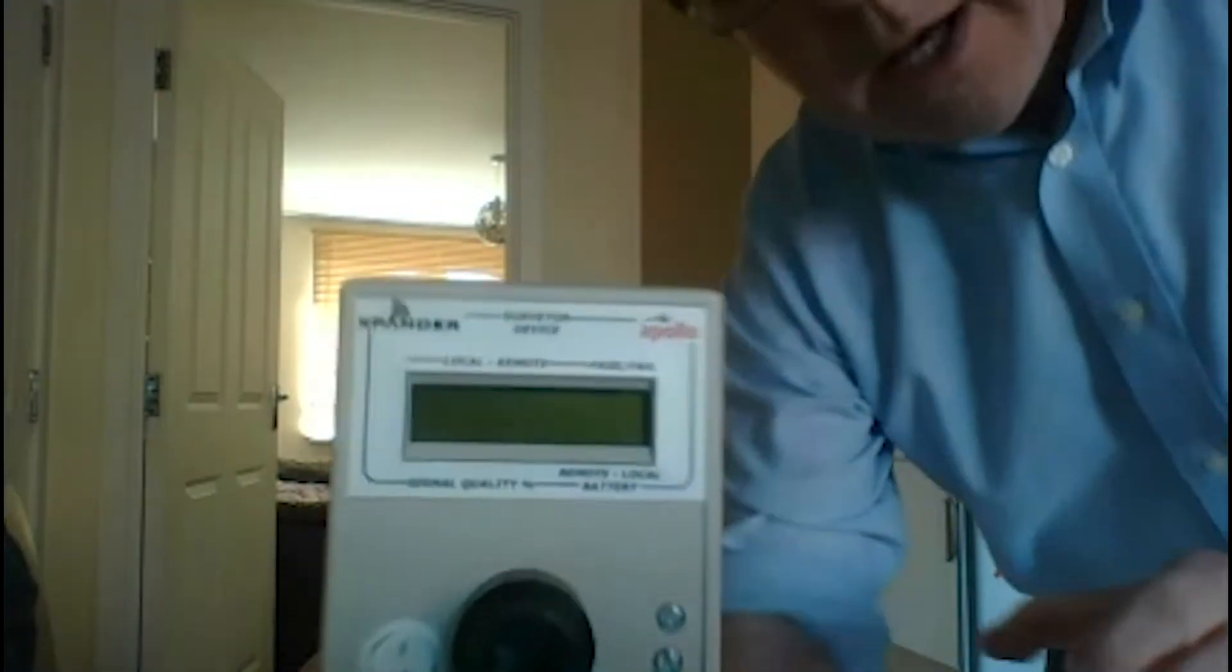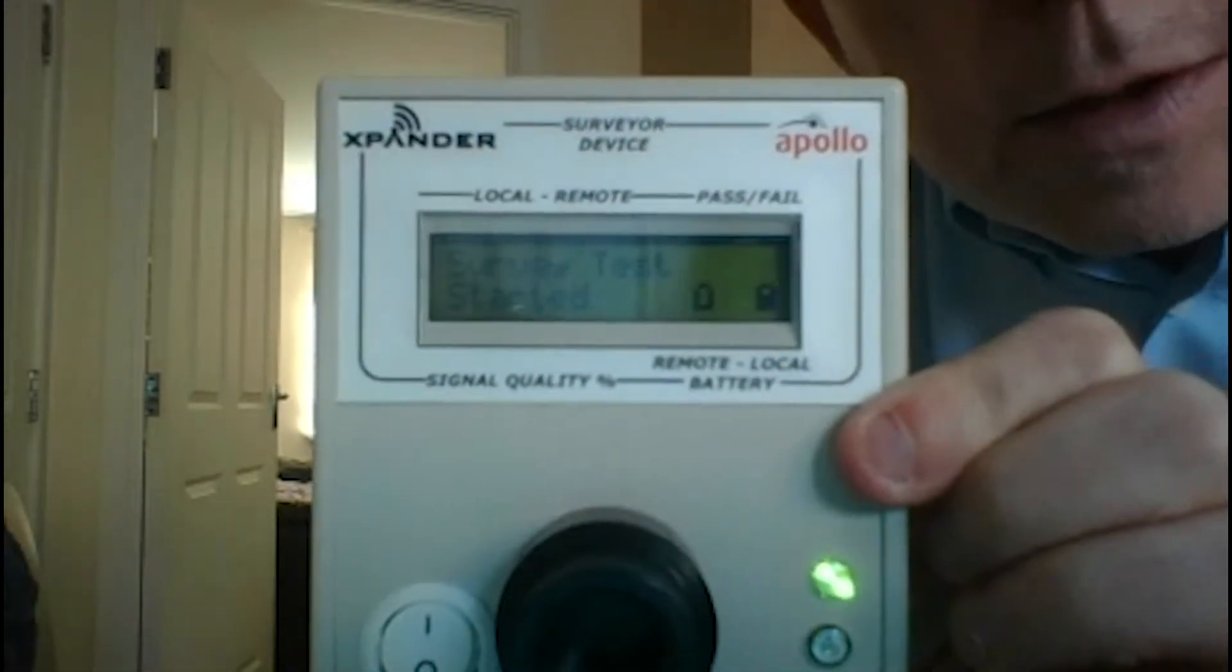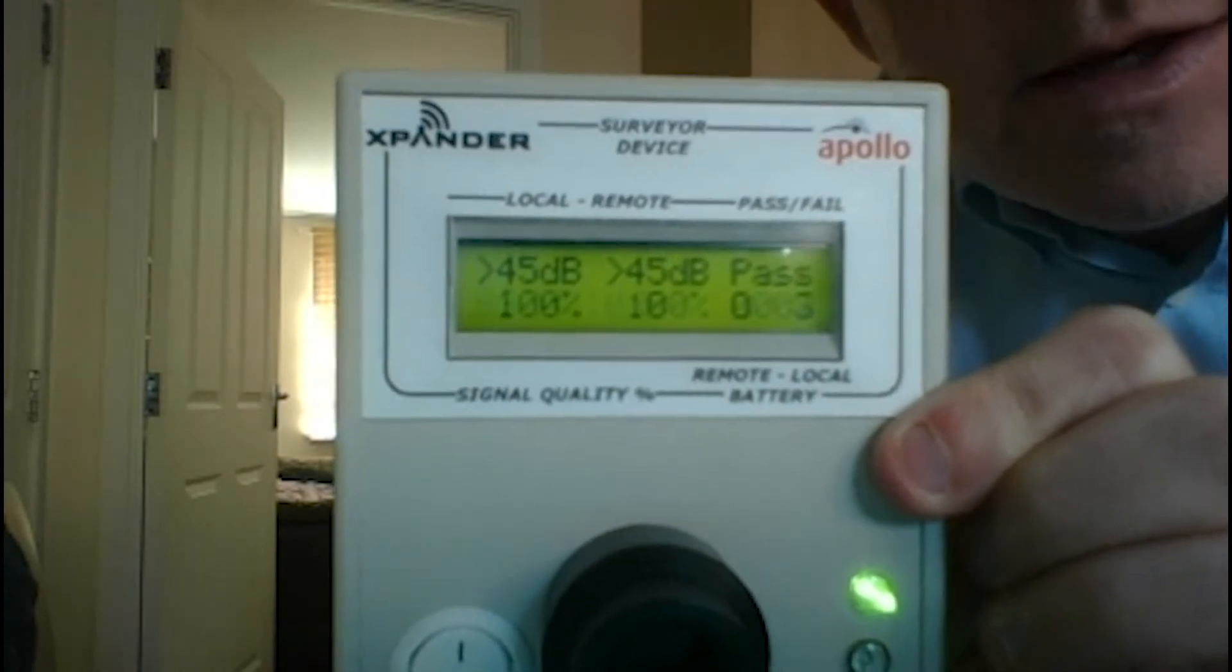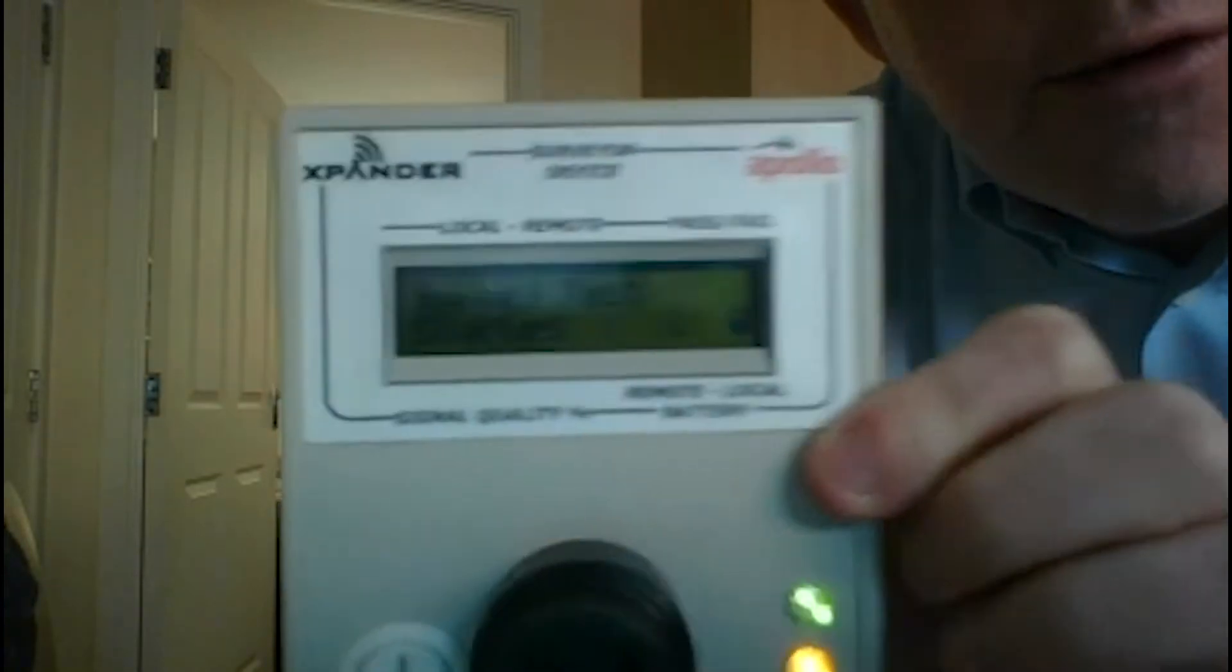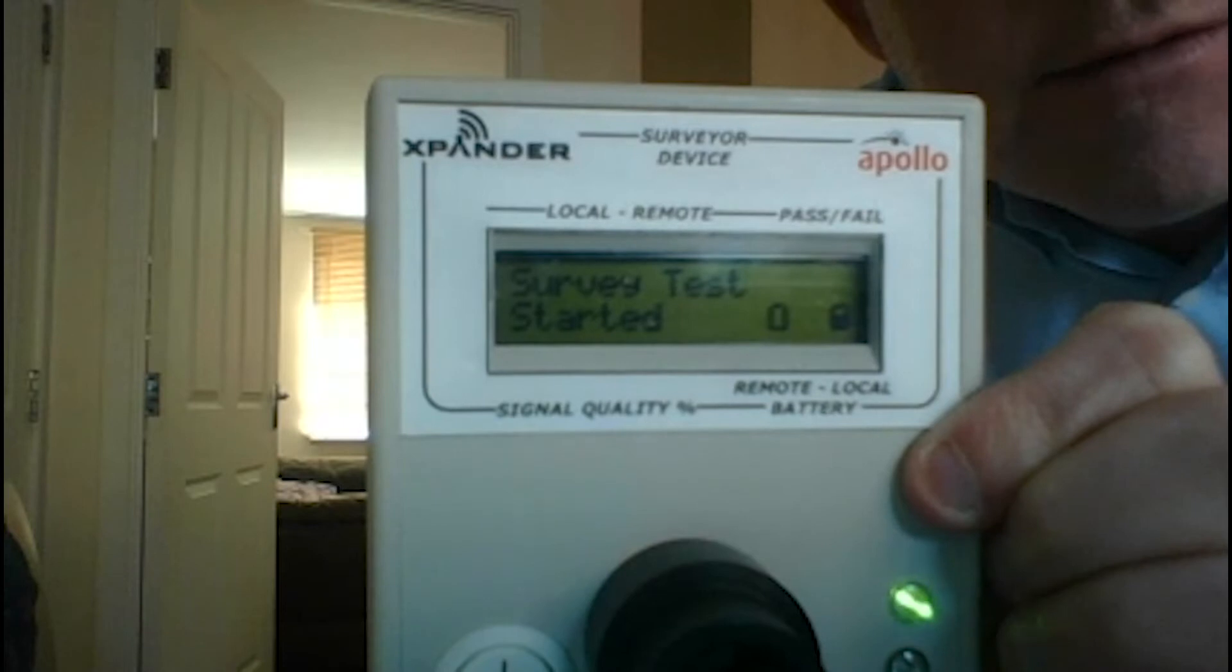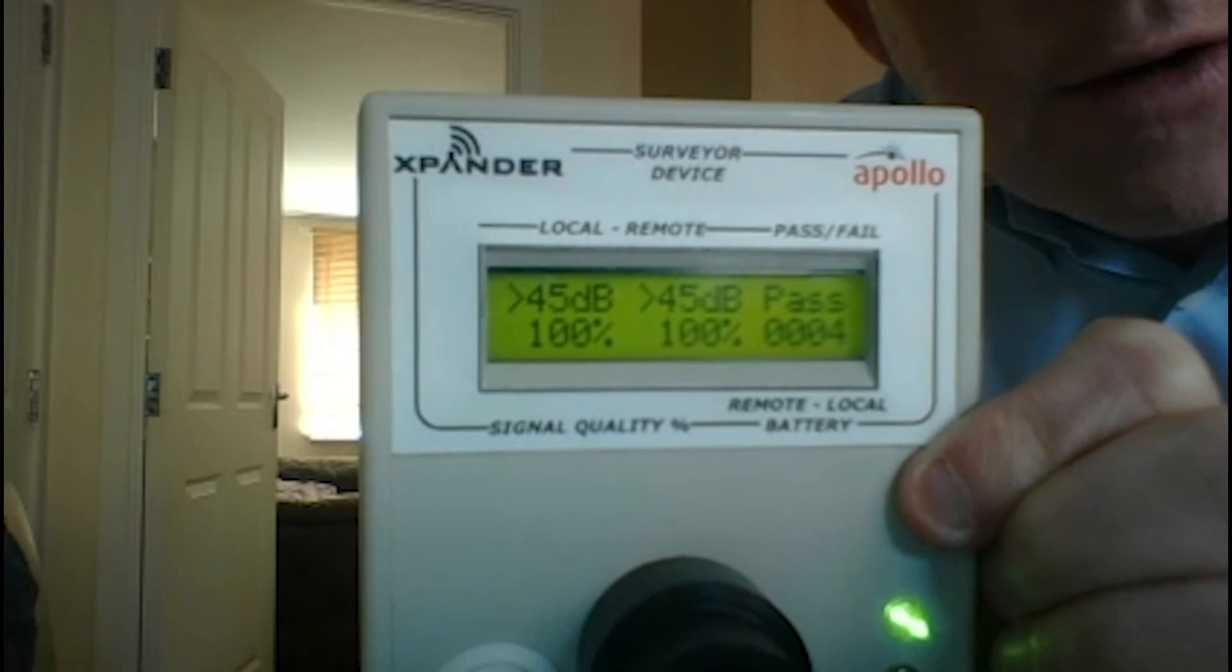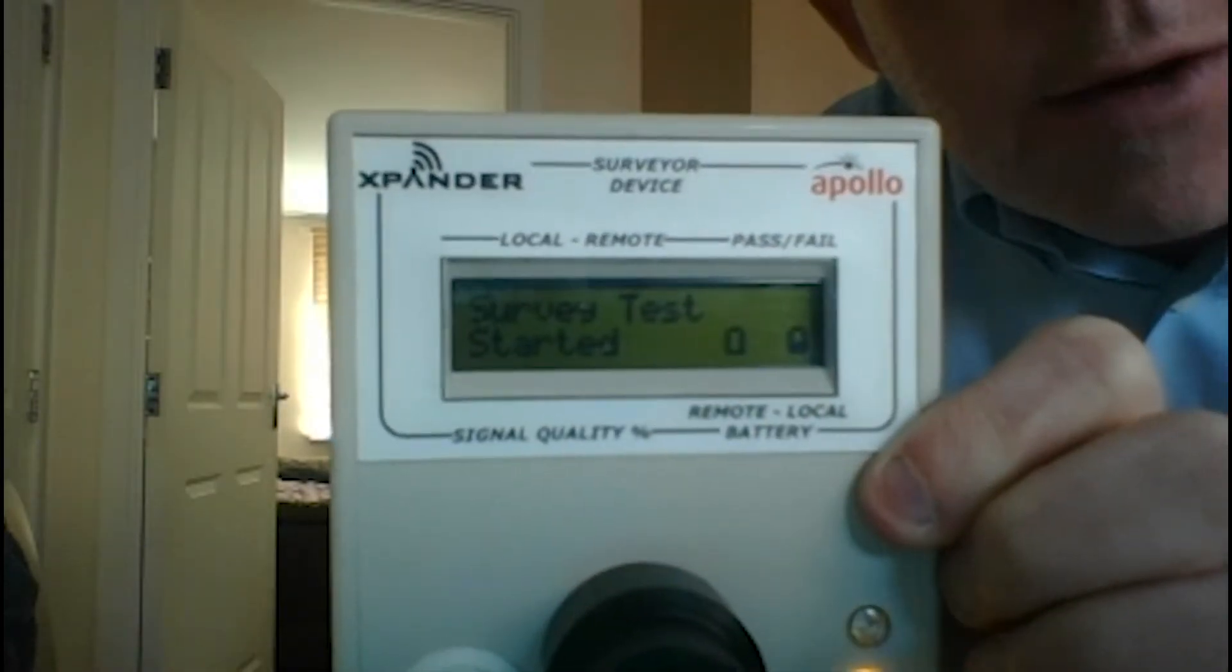Okay, so as I was saying, every time you put this up to the wall, some lights flash and you get a reading. 45 dBs - the dB reading is what you're looking for. And 45 dBs is obviously the best reading. The lowest you ever want to see is 25 dBs, so anything below 25 dBs is going to give you a fail.